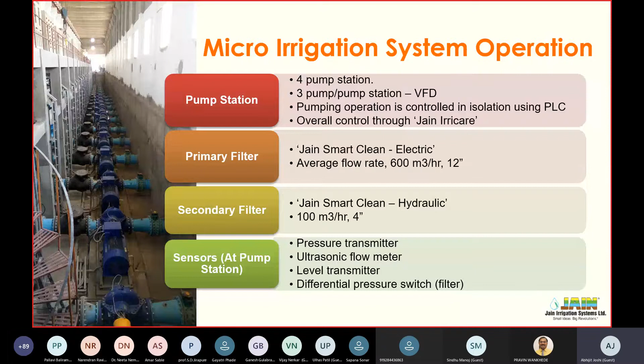And very important, there are sensors provided. At the pump station, there are pressure transmitters, flow transmitters, level transmitters, and differential pressure transmitters or switches, which will tell you when to flush the filters. These sensors are continuously providing their data to the Irricare system, and ultimately through Irricare, we control the pumping operations for these schemes.